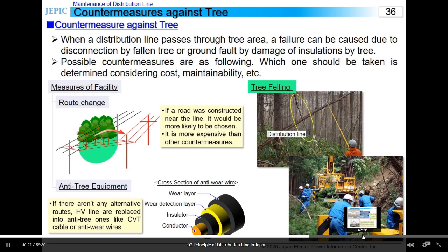In this slide, I explain about measures against trees. Distribution lines often pass through areas with lots of trees, and in such cases, a failure might happen due to disconnection by fallen trees or a ground fault by damage of insulation. As a maintenance of such facilities, there are two types of countermeasures. One is measures of facility, another is tree felling. Which measures should be taken is determined taking into consideration cost or maintainability, etc.